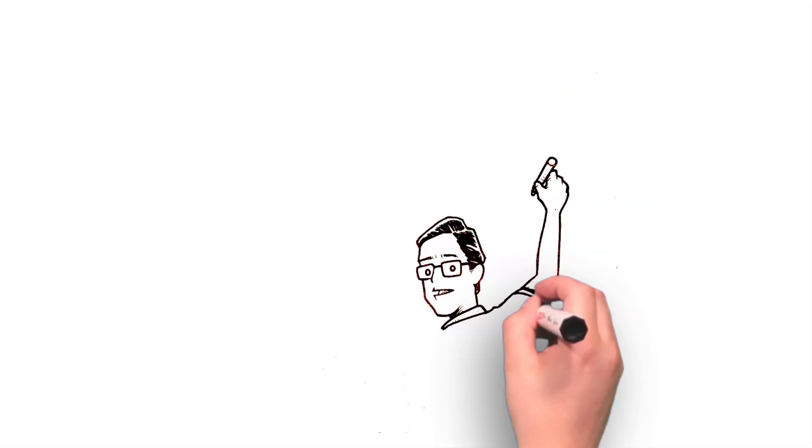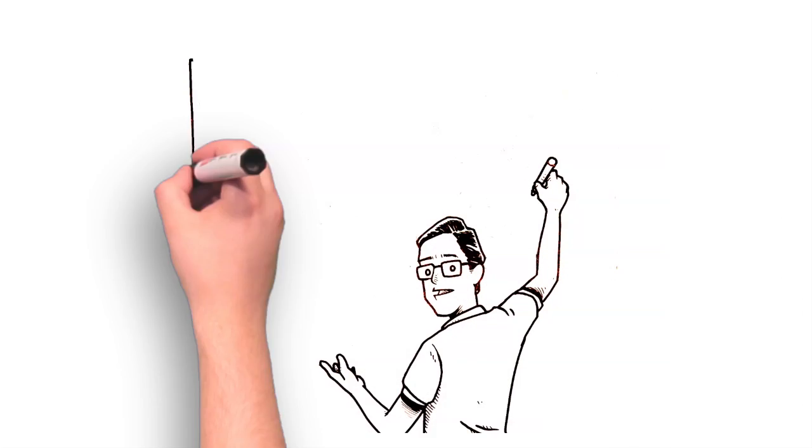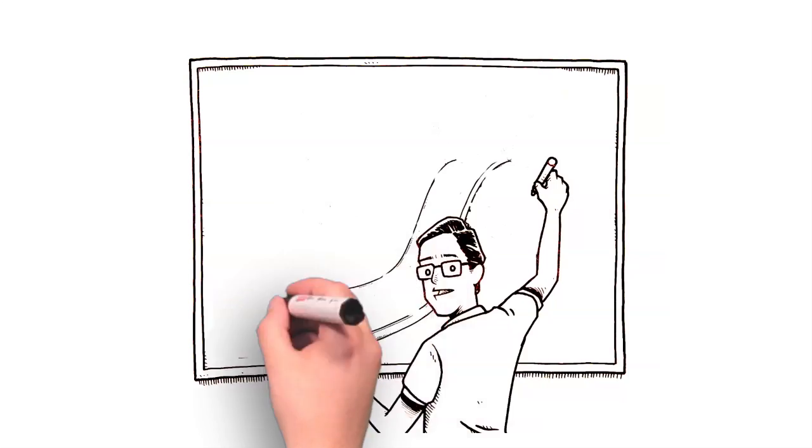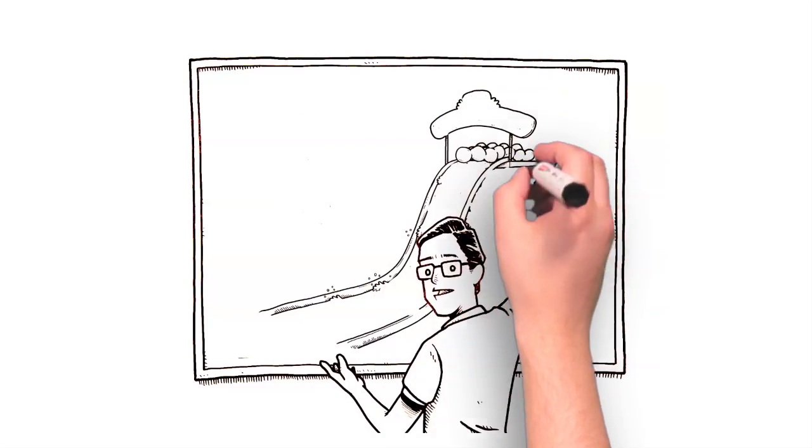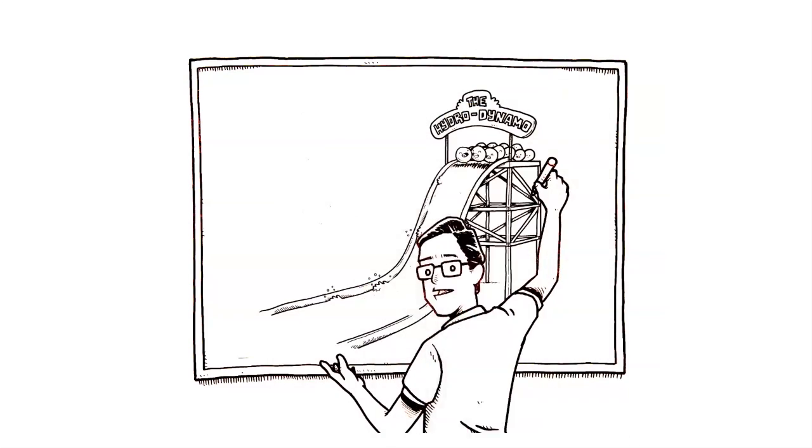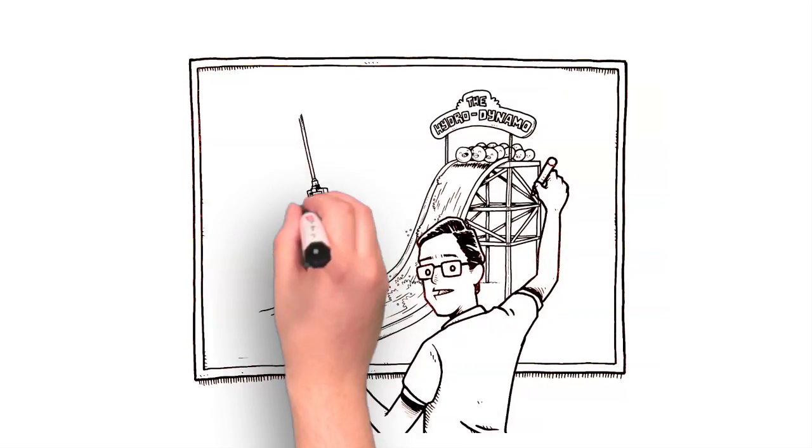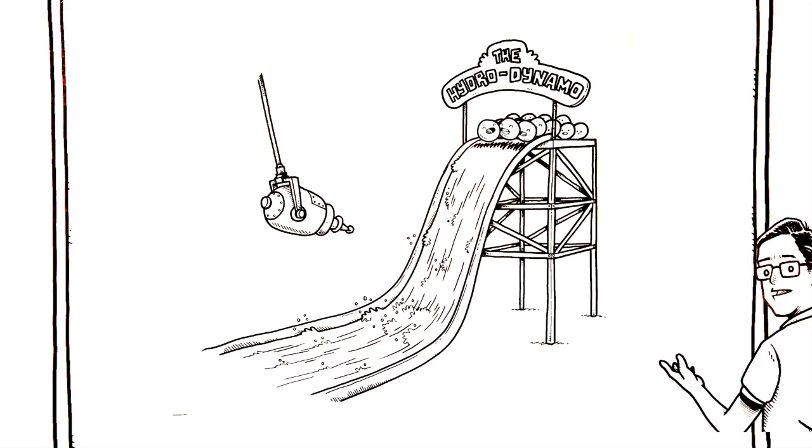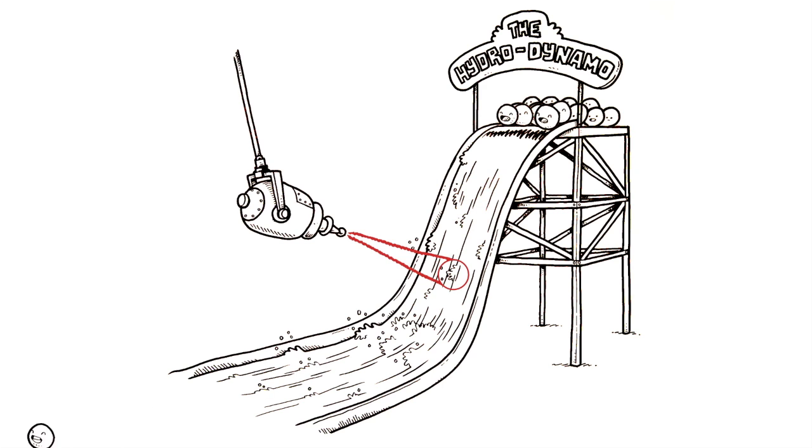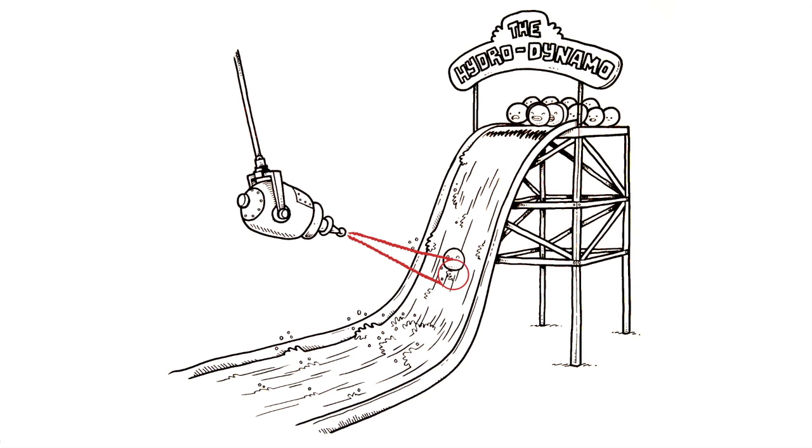Well, conventional flow cytometry uses hydrodynamic focusing to move and maintain particles or cells at the center of an interrogating laser's path. This system uses a rapidly moving sheath fluid to pull particles or cells into a central core and then to pass them in front of a laser that can then read scatter and fluorescent signals from the particles or cells.